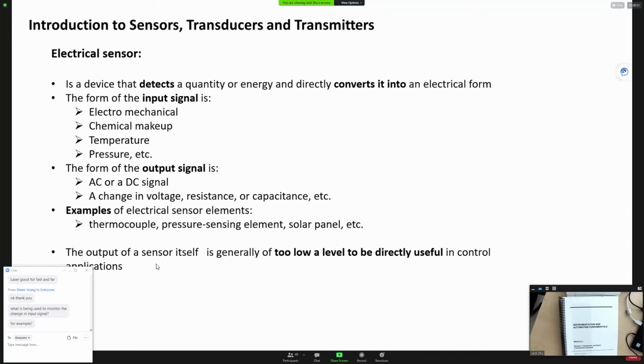A normal electrical sensor, even if it can output an electrical signal, doesn't matter whether AC or DC, or voltage, resistance, or current, the signal is usually too low. So we cannot use those directly to control something. We usually have to put in an amplifier to increase the signal amplitude or magnitude, then go to the control application.